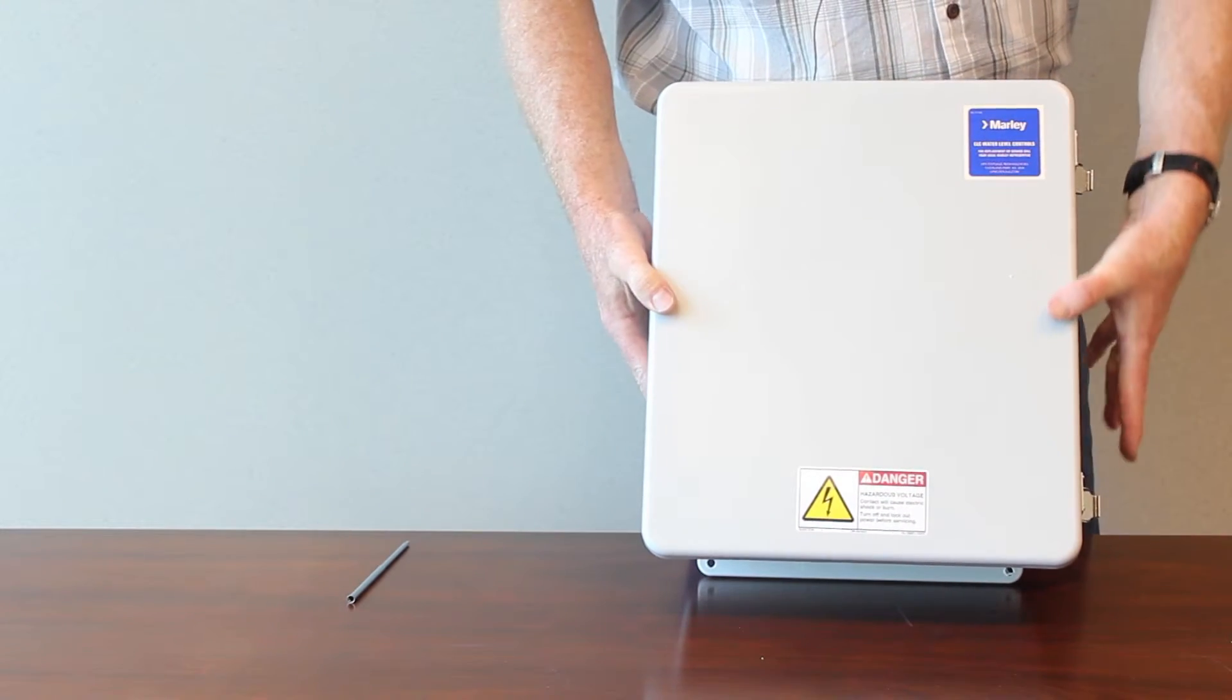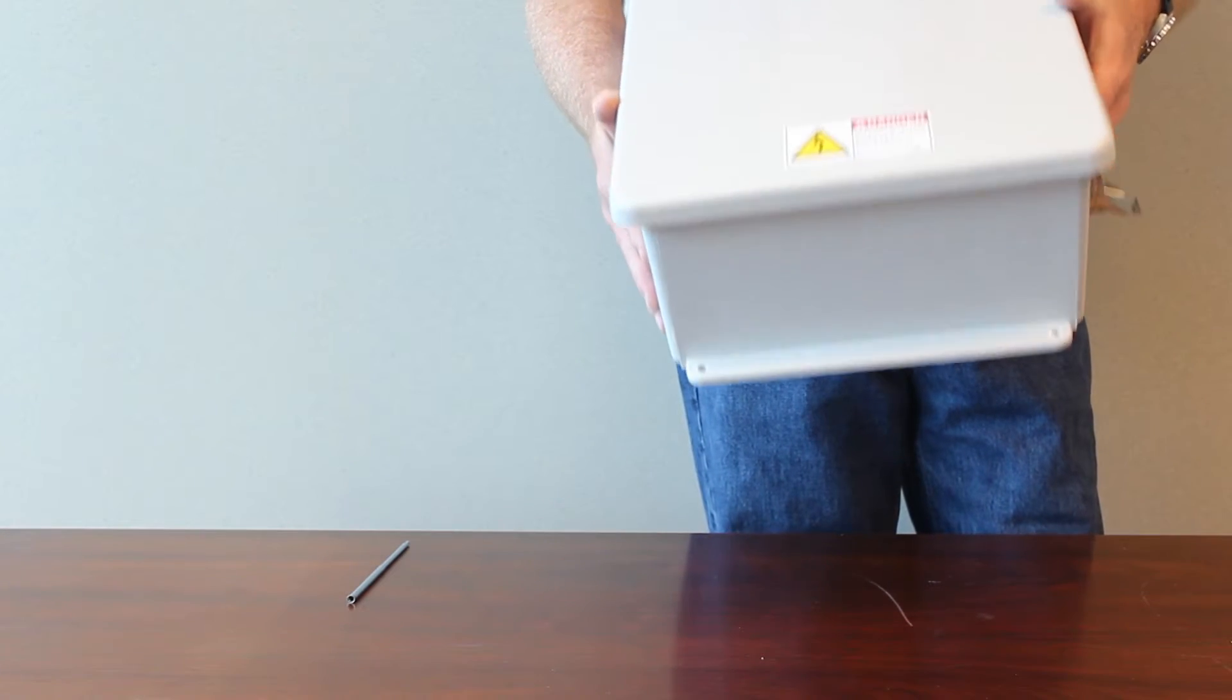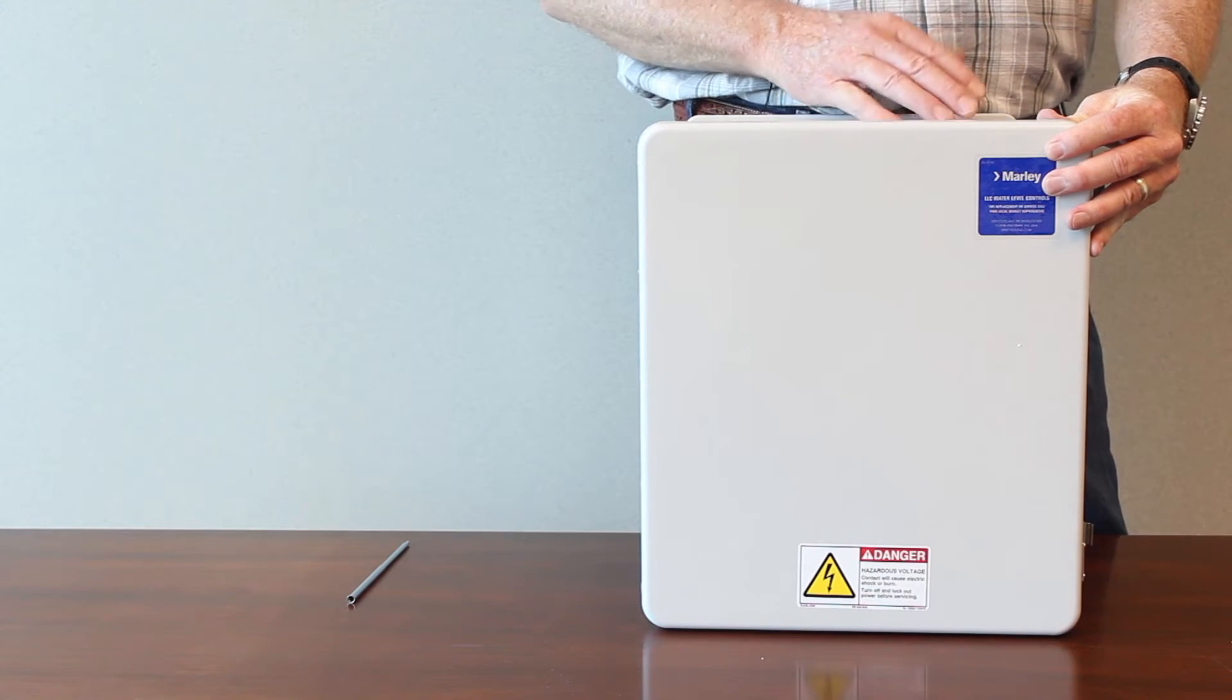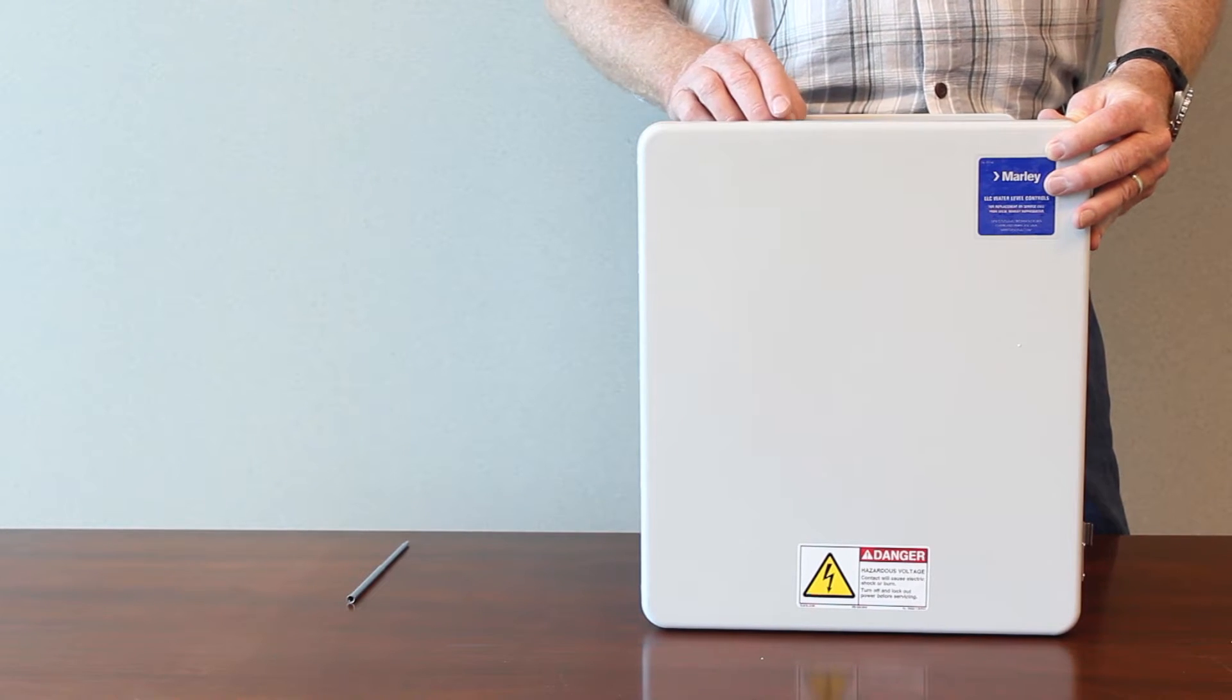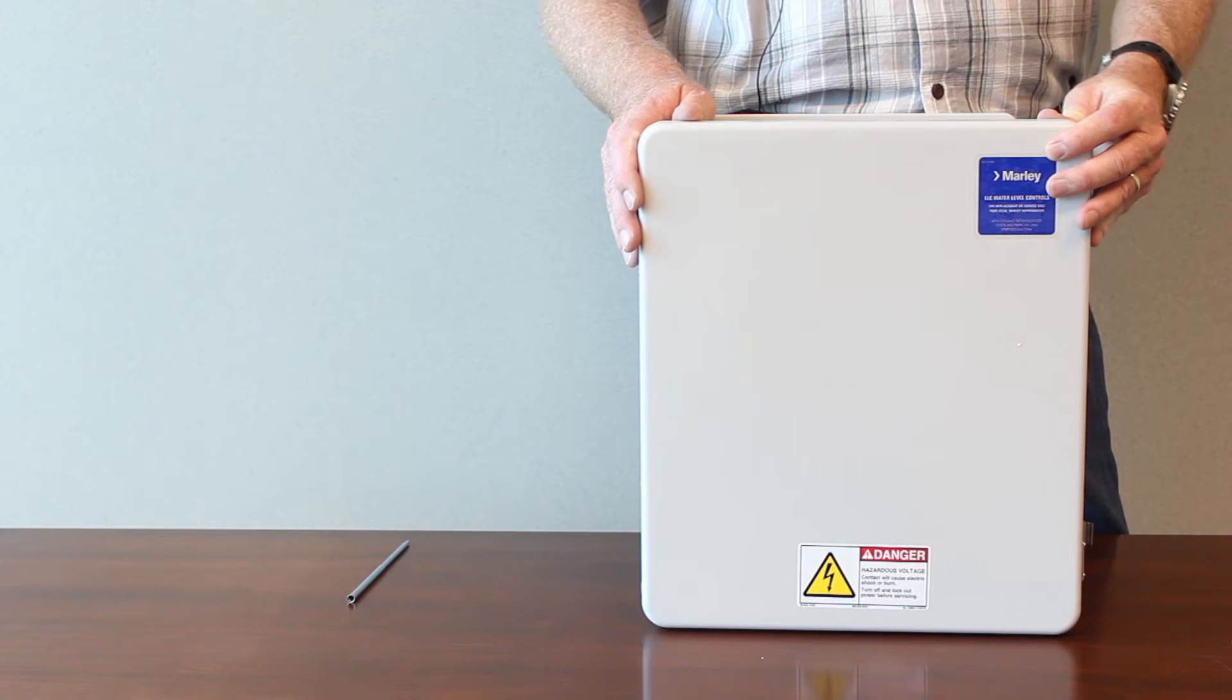Make sure all your conduits come into the bottom of the control panel. Conduits coming into the top of an outdoor enclosure, whether it's this rating or any other rating, is really not a good idea because water can seep in and this being a watertight enclosure if water gets in it can't get back out. So it's very common best practice to run your conduits into the bottom of the control panel.